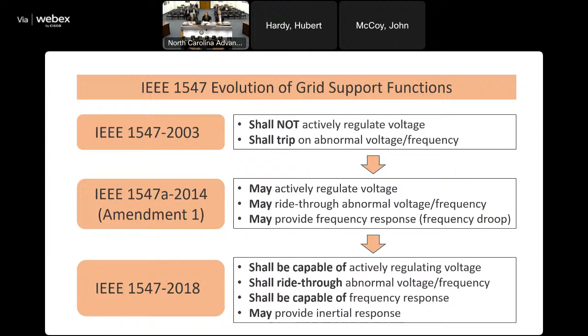As renewables became more common and there was a lot more on the grid, utilities and developers both said we might want to do some of these things, like regulate voltage — why shouldn't we if we have the ability? And why do we want to trip offline when we might need the site online? So in 2014, the standard was amended to say it may regulate voltage and ride through these abnormal conditions, as long as the utility agrees. Ultimately in 2018, the current version says these sites need to at least be capable of doing that. The utility can still decide not to, but it has to be capable of regulating voltage and riding through these abnormal events.